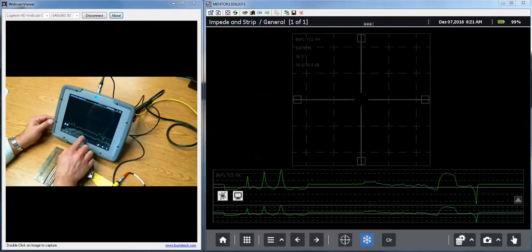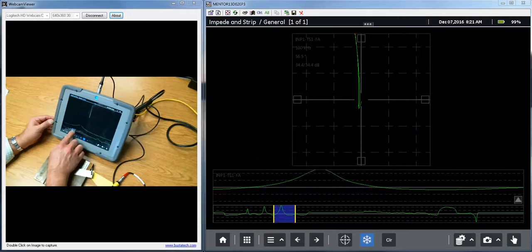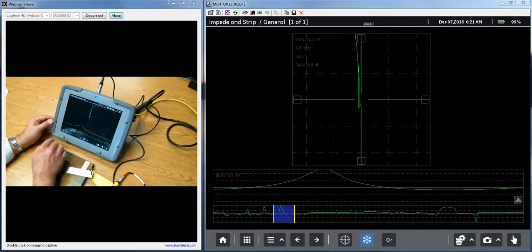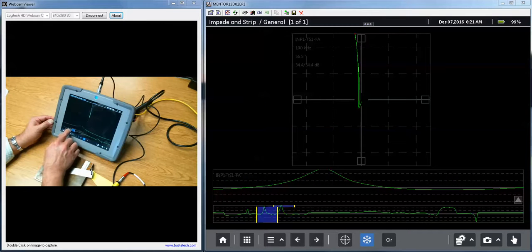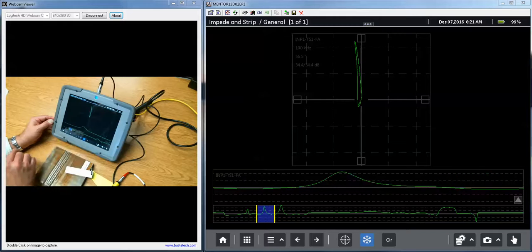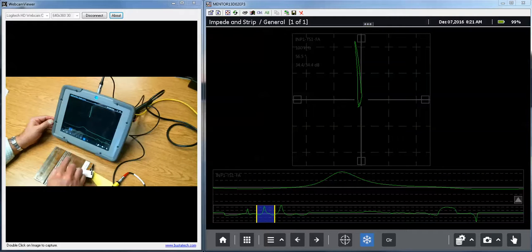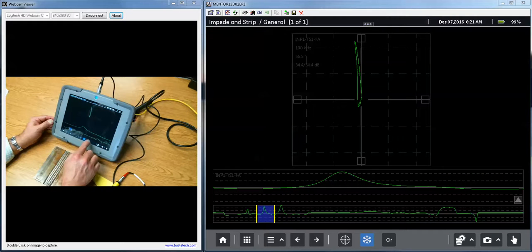I can open an overview. I can take my finger and place a set of cursors down and select an indication of interest. So there you see the notch, the one millimeter deep notch in the standard.